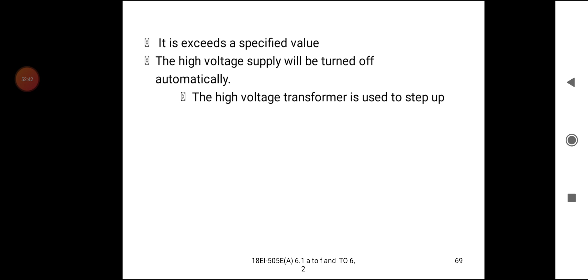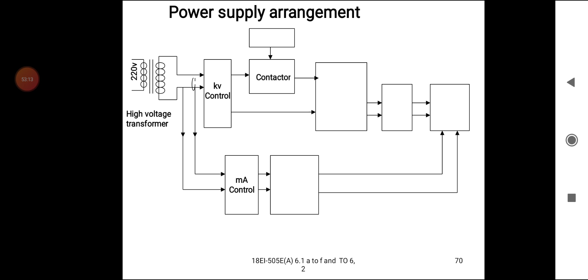The high voltage transformer is used to step up the voltage in the power supply arrangement. A 220 volts supply goes to the primary winding of the transformer, and the high voltage comes from the secondary winding. Other parts are the kilovolts control, milliamps control, contactor, timer, high voltage transformer, tube filament transformer, high voltage rectifier, and X-ray tube. This is a power supply arrangement for the X-ray tube.